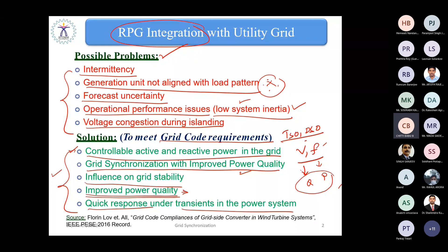However, the following conditions should be met, corresponding to voltage in RMS measured at the point of common coupling. As far as power quality is concerned, when the voltage at the point of common coupling deviates between nominal and 50% of the nominal, the inverter should be tripped in 0.1 seconds. It implies 100 milliseconds. When the voltage is between 50 and 85%, the tripping time would be 2 seconds. When the voltage variation is between 85% and 110% of the nominal, the inverter still feeds power to the utility grid. When the voltage is between 110% and 135% of the nominal, the tripping time would be 2 seconds. When the voltage exceeds 135% of the nominal, the tripping time would be 0.05 seconds.